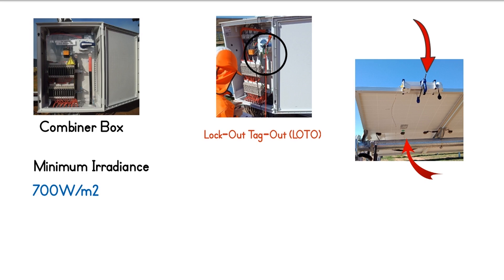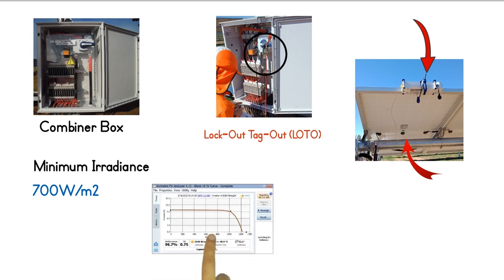If a string under test is performing normally, the IV curve has a normal shape and will closely approximate the predicted maximum power. Otherwise, the IV curve will have some deviations from the normal curve.